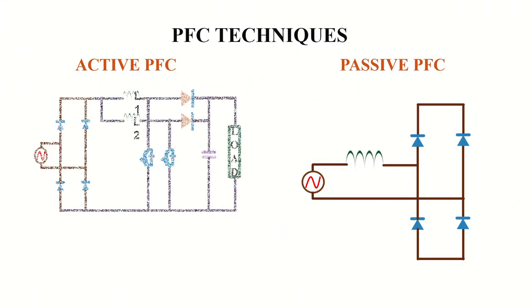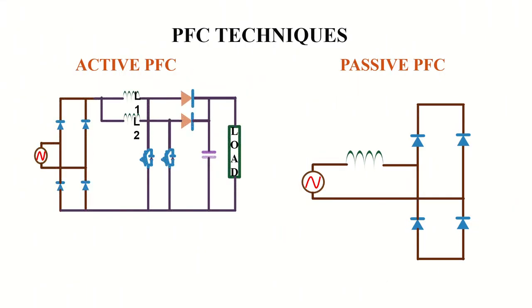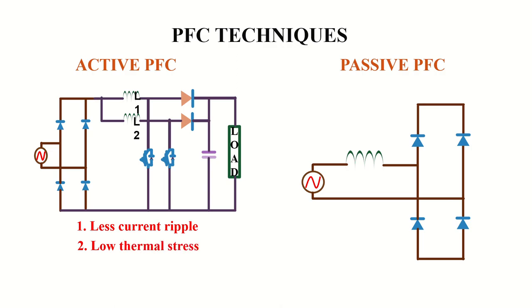Another commonly used PFC circuit is the interleaved boost converter. Interleaving has the advantage of less current ripple and hence, the low value of input capacitance can be used. This topology mostly used in high power applications. Interleaving also makes it possible to reduce the size of inductors, diodes, and switches since the total thermal stress is low compared to normal boost rectifier.